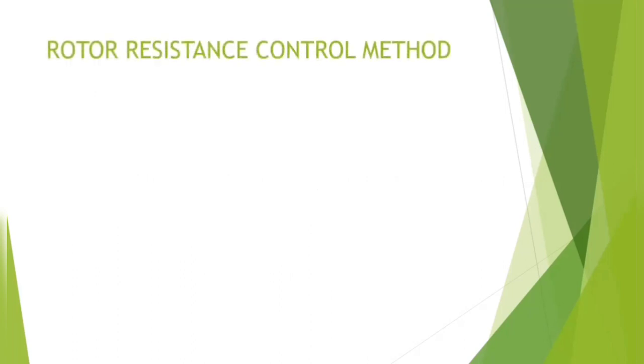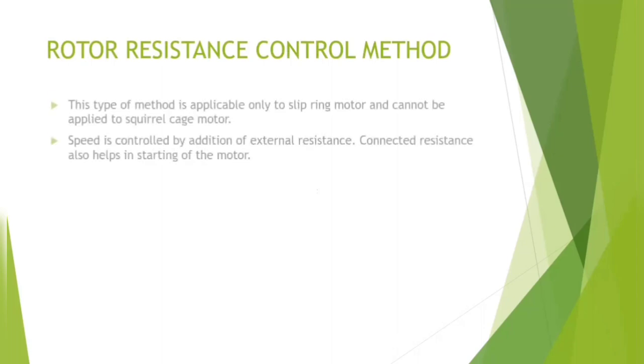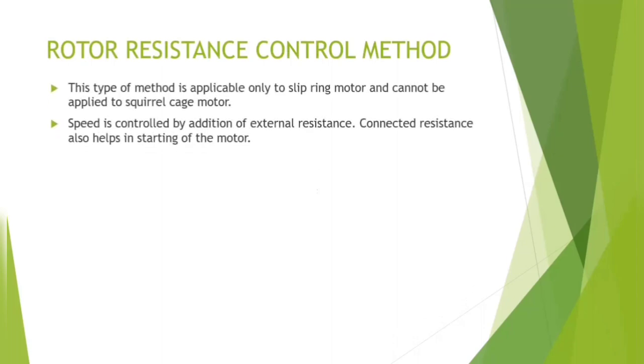Coming to second method, the rotor resistance control method. This type of method is applicable only to slip ring motor and cannot be applied to squirrel cage motor. The speed is controlled by addition of the external resistance, and connected resistance has a dual purpose: it helps in starting of the motor and also speed controlling.